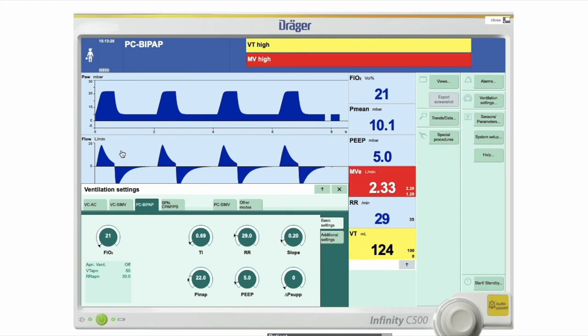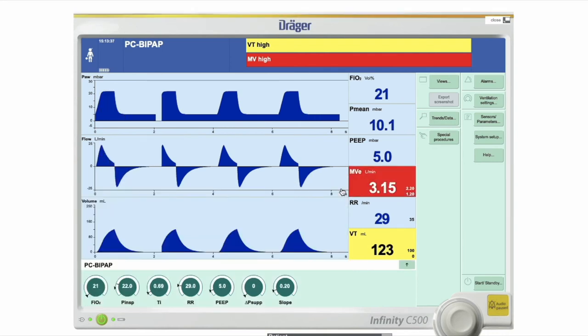Right, we'll talk about these little things in a moment, but we appear to have alarms. Based on these settings, close this, two alarms have sprung up. One is a medium priority alarm, and the medium priority alarm will make this flash yellow at the top. It means, especially with tidal volumes, that your tidal volumes are too high. You need to decide to do something to reduce the tidal volume.